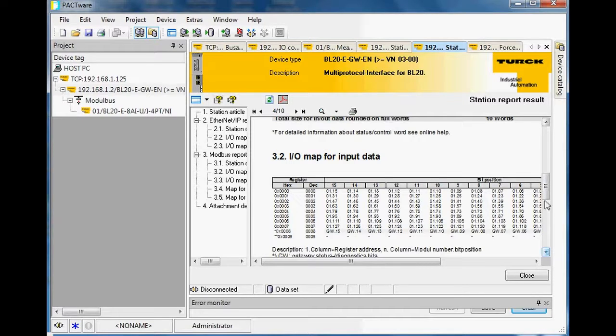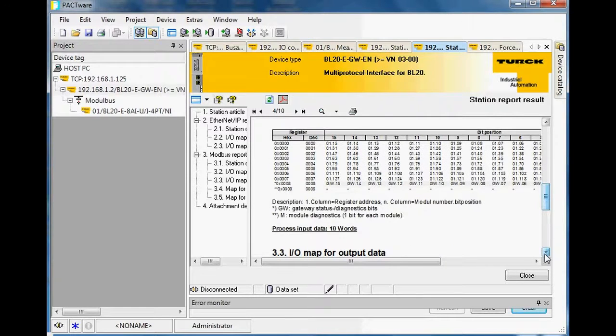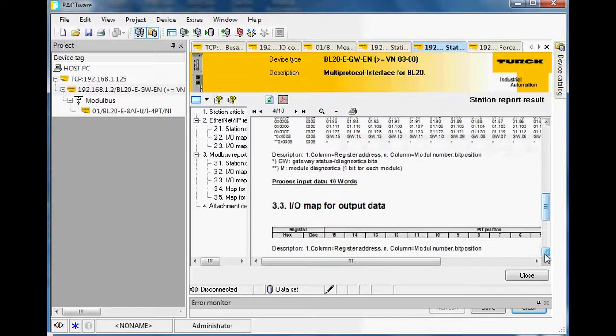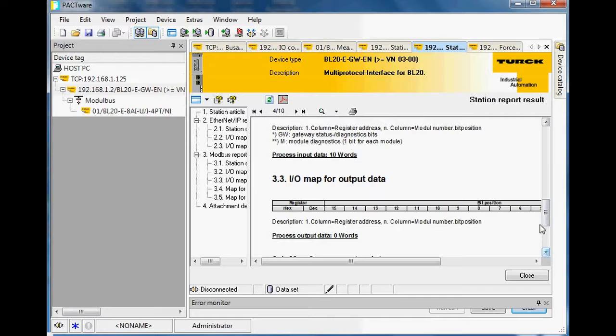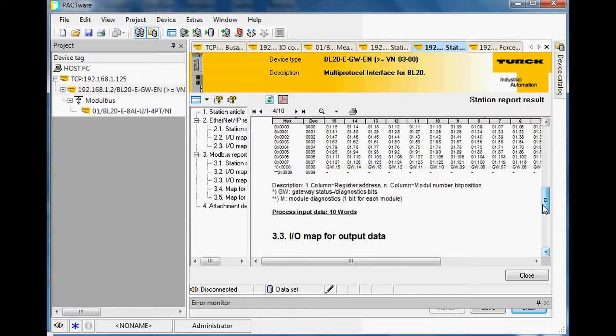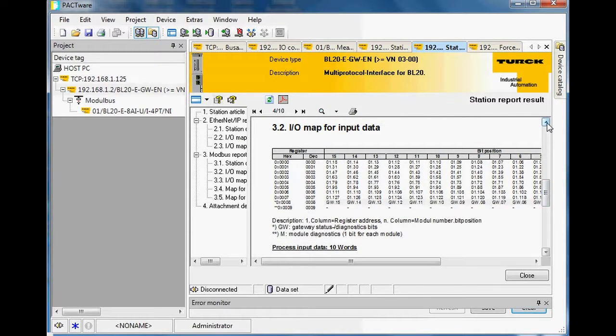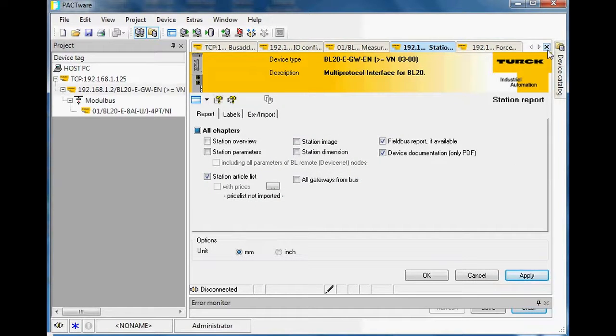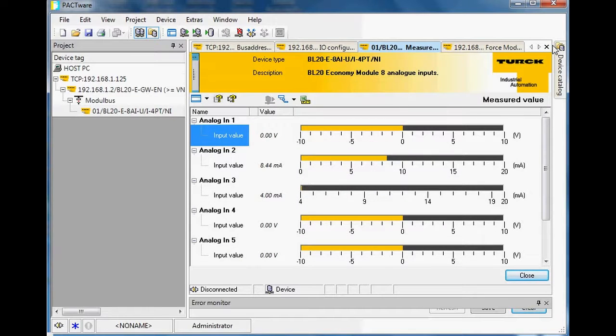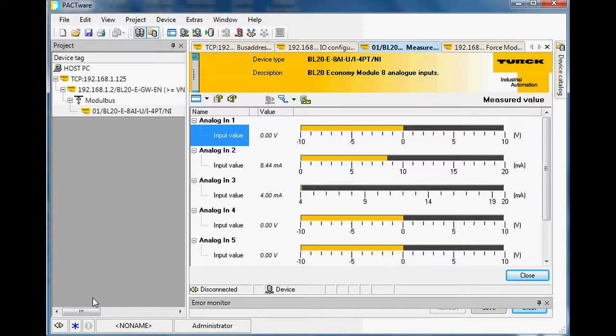These all start at zero, but when using a Red Lion product you add one to those numbers, so the range is 40001 to 40010 for all the data. This node has no outputs, so the output data section shows no words — everything is inputs. All the analog IO maps from 40001 to 40010. I like using Pactware because it lets me build a node correctly with no mistakes. That's a quick video on how to use Pactware to interact with your BL20 IO — thanks, have a great day.